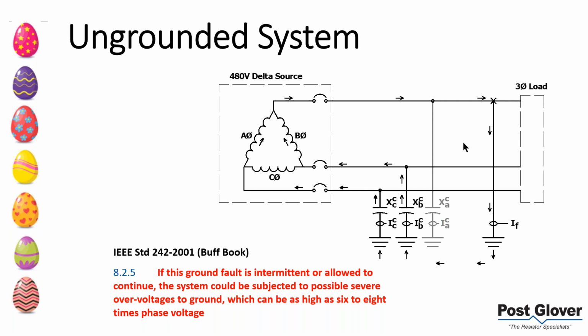But anyway, when you have an intermittent fault, the system's capacitance charges up, and that's what creates the overvoltage on the system. That's where you can get, like IEEE talks about, 6 to 8 times your nominal voltage. That's a lot. That's 3,000 volts roughly, 3 to 4.